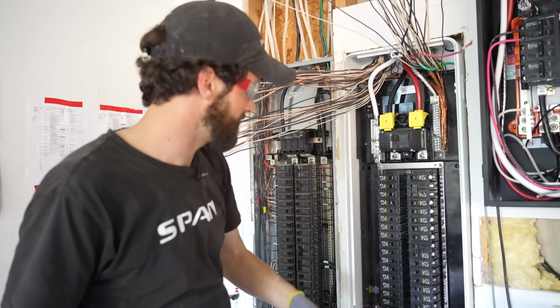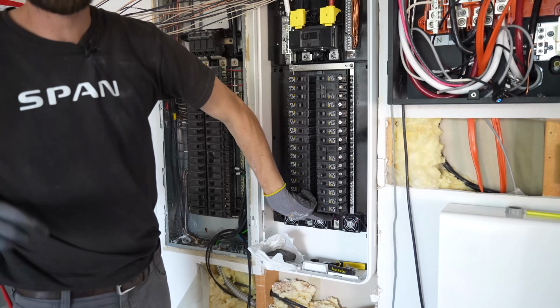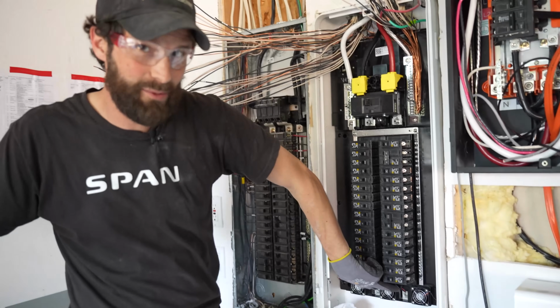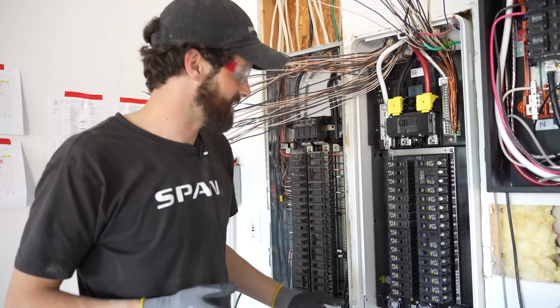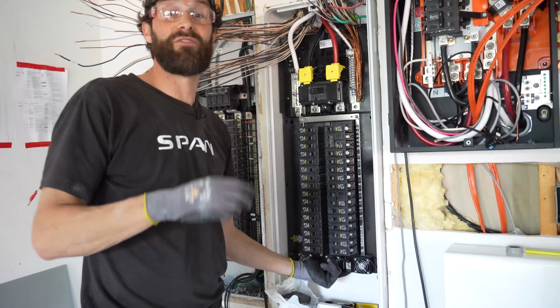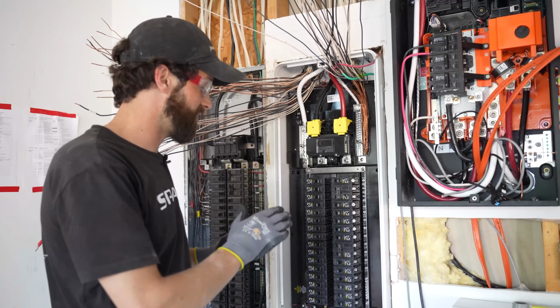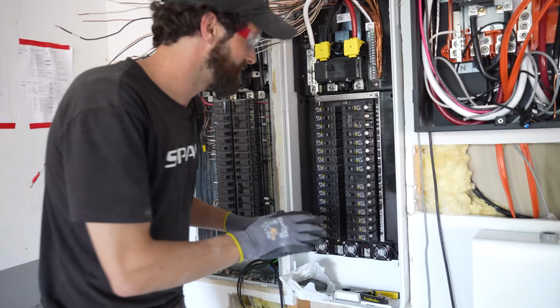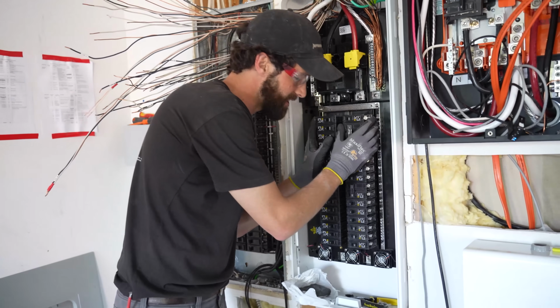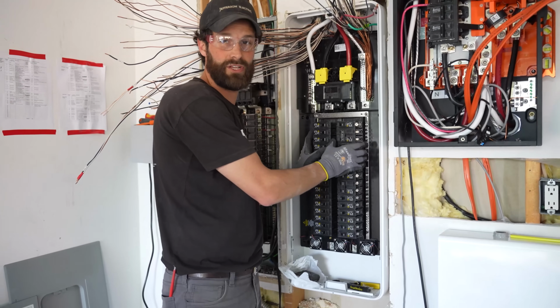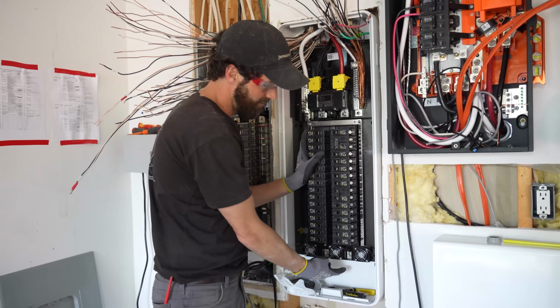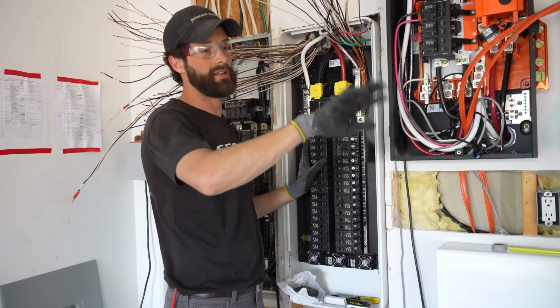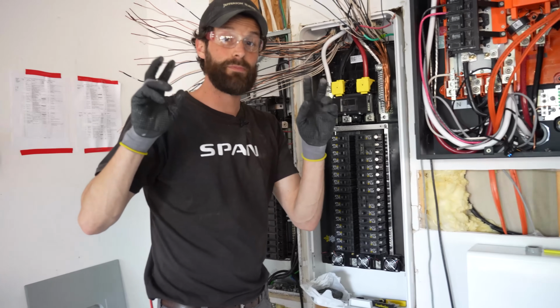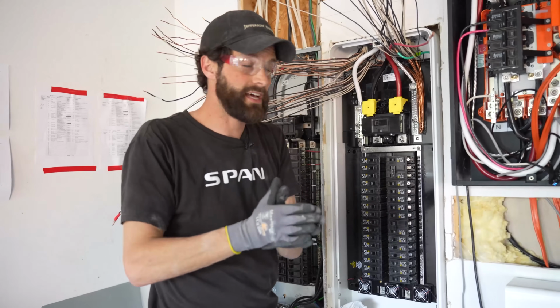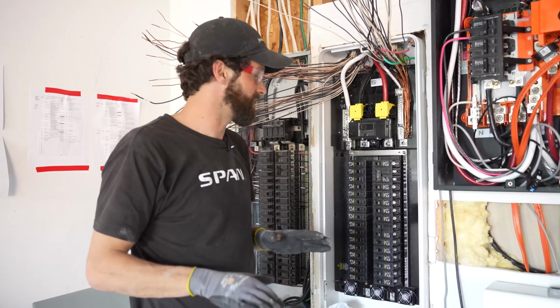They've also got feed-through lugs at the bottom, which I love. That's a must in every panel in my opinion, but it's not a reality in every panel. So you can feed through full 200 amps from the span. Now if you do that, span is only monitoring these circuits, the only microchip-connected circuits. So if you feed whatever the sub panel is, it's not going to have the span circuit-level intelligence. That's strictly just a set of feed-through lugs for a sub.